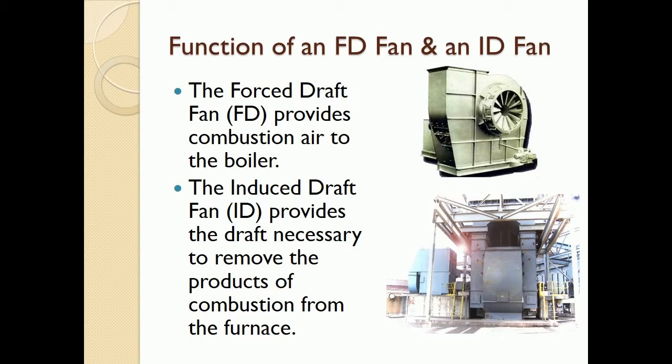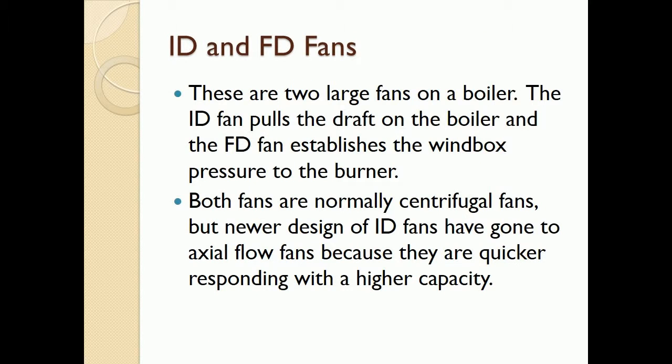What are the functions of the FD fan and the ID fan? The forced draft fan, FD, provides combustion air to the boiler. The induced draft fan, ID, provides the draft necessary to remove the products of combustion from the furnace. The ID and FD fans are two large fans on a boiler.